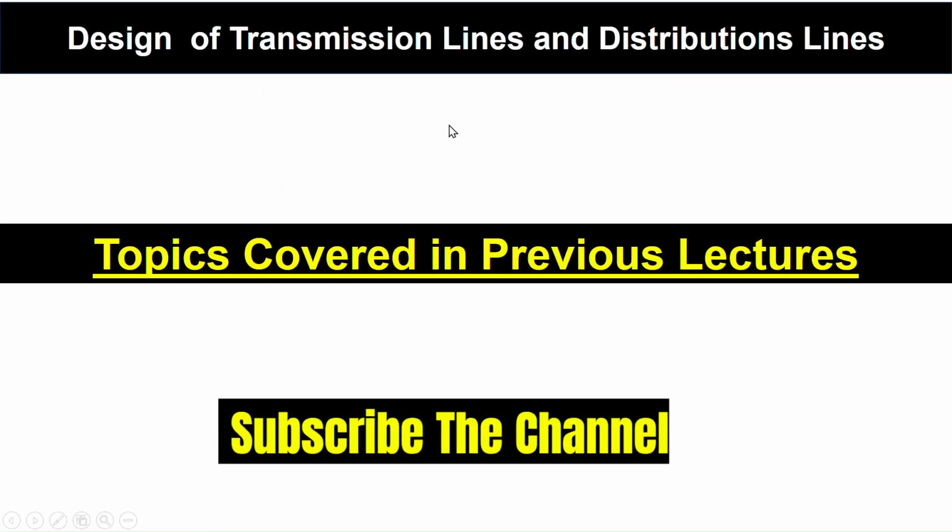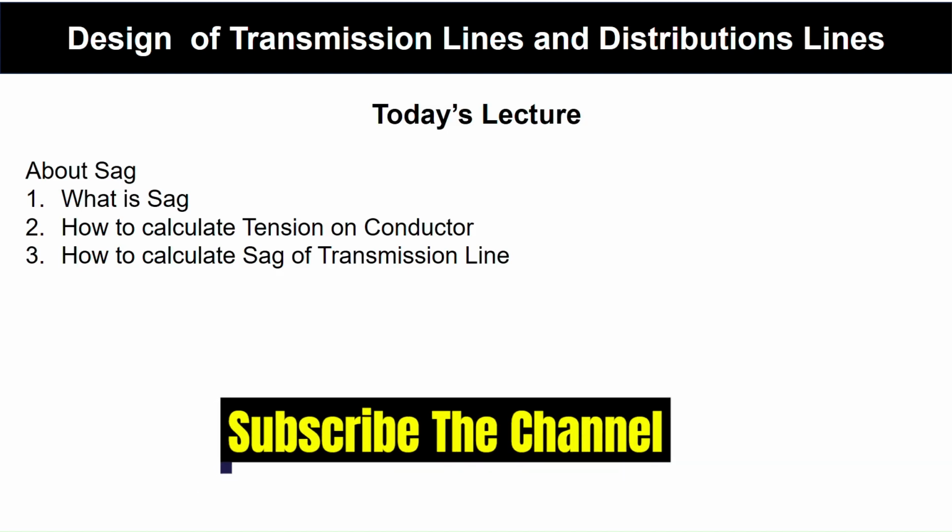Now, today's lecture is about the sag. What is sag? How to calculate tension on a conductor? How to calculate sag of a transmission line? Here we can take an example and calculate the sag of a transmission line and the tension on a conductor, and see how we can calculate these things practically on a field.